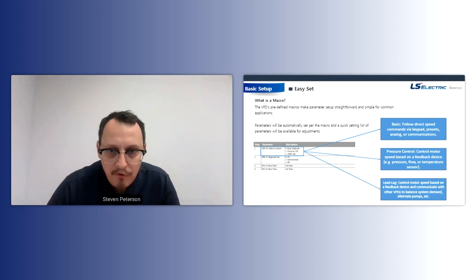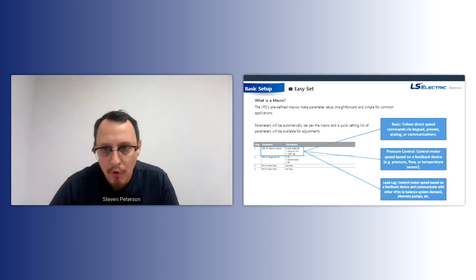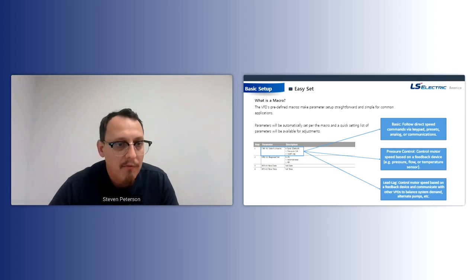The other 2 are pressure control and lead lag, and they're kind of similar. Pressure control is actually called a simplex operation. So it's just one drive that's controlling motor speed based on a feedback device, such as a pressure transducer, maybe a flow meter, or a temperature sensor. It could even be like a level sensor, okay? So that's actually a PID loop that's happening within the drive. So we'll talk about that as we go along here.